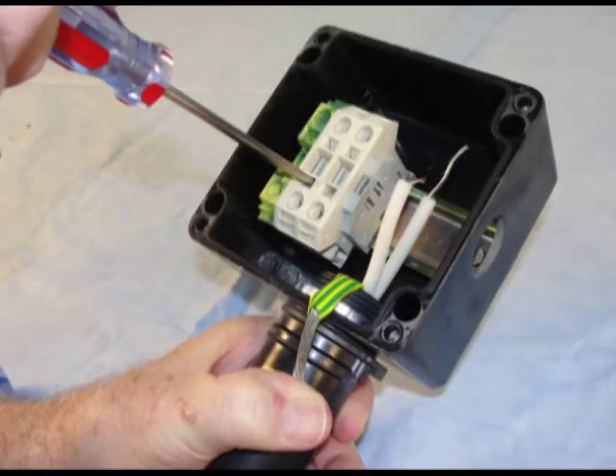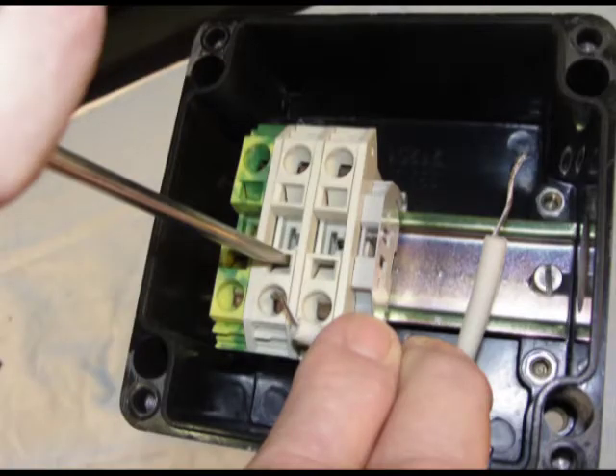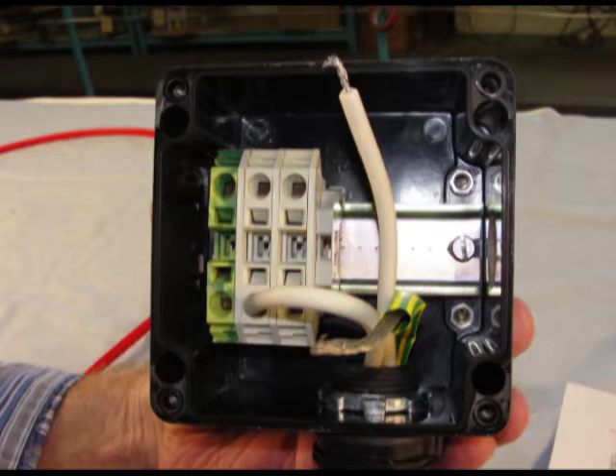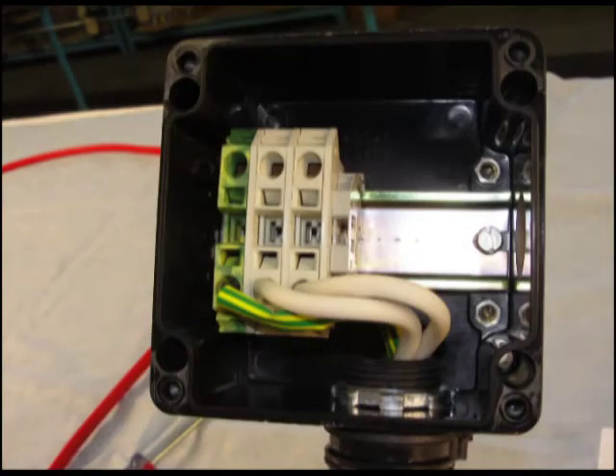This kit uses spring clamp style terminals. To connect wires, firmly insert a slotted screwdriver into the square hole to open the spring. When fully inserted, the screwdriver will lock into place, allowing you to remove your hand and insert the wire into the round hole. Remove the screwdriver to clamp the wire. The wire is held securely against the bus bar. Repeat this process for all connections.